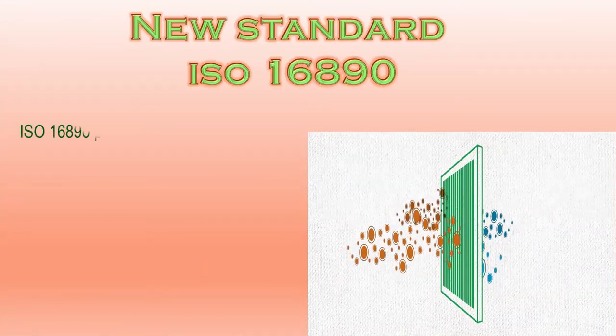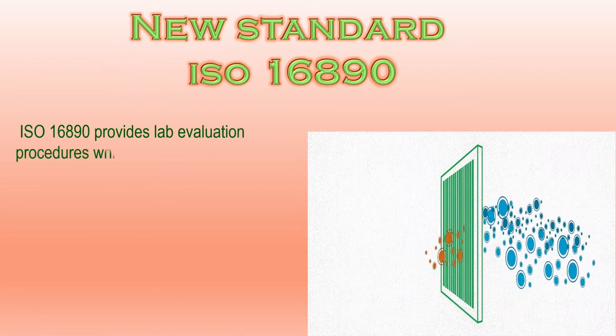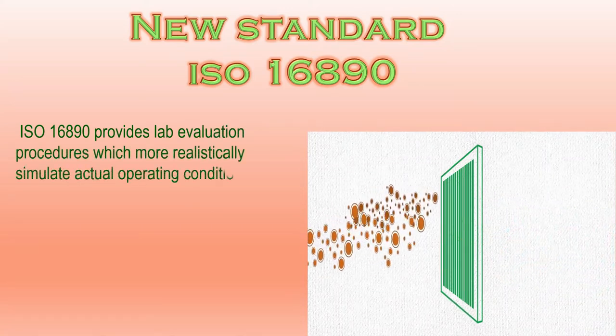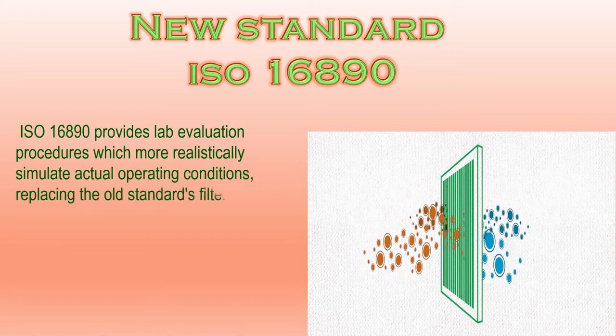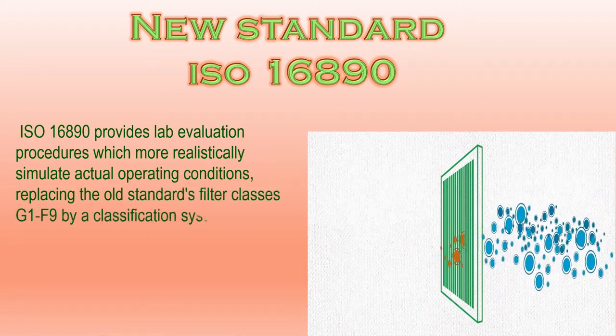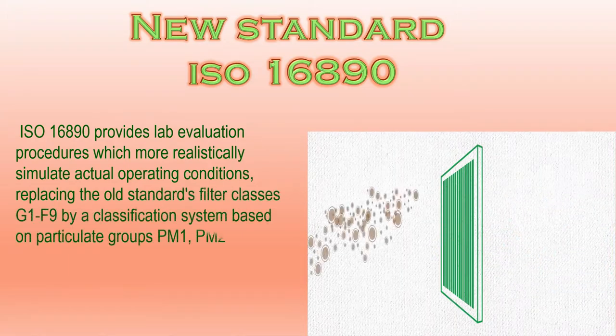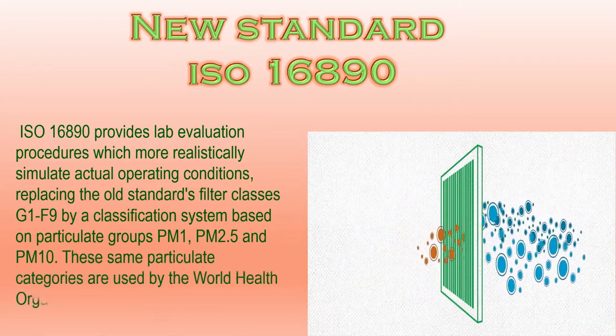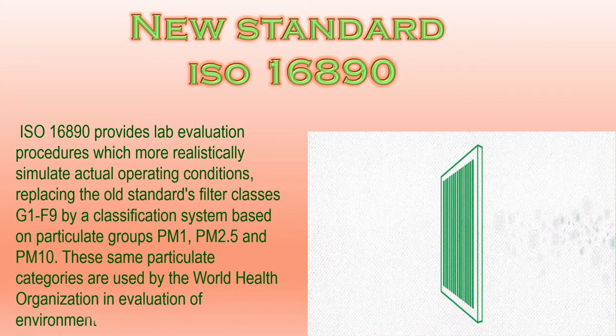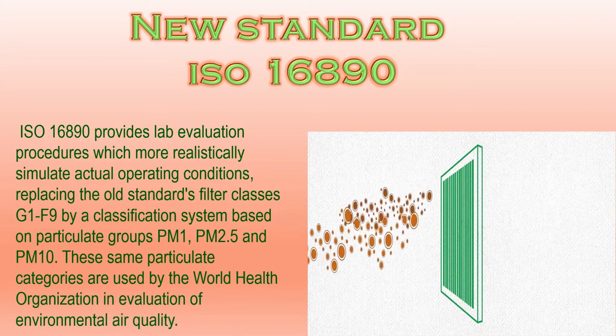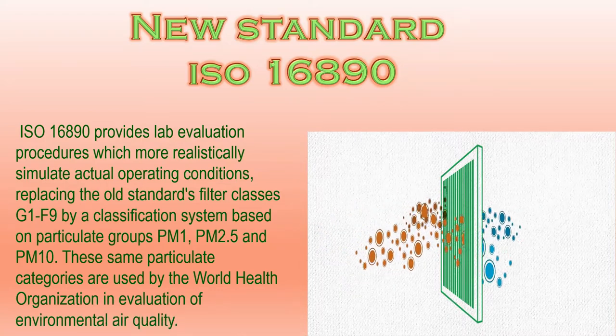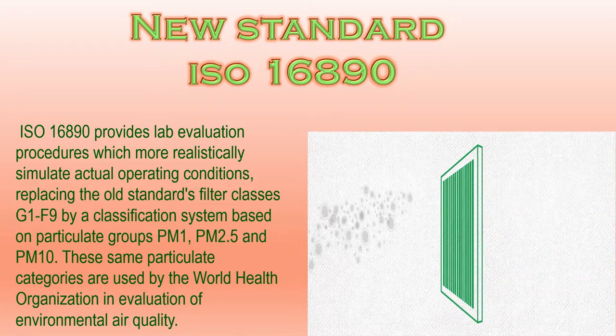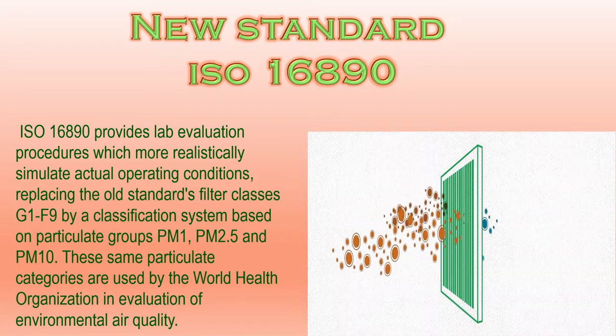ISO 16890 provides lab evaluation procedures which more realistically simulate actual operating conditions. It replaces the old filter classes G1 to F9 with a classification system based on particulate groups PM1, PM2.5, and PM10. These same particulate categories are used by the World Health Organization in evaluation of environmental air quality.